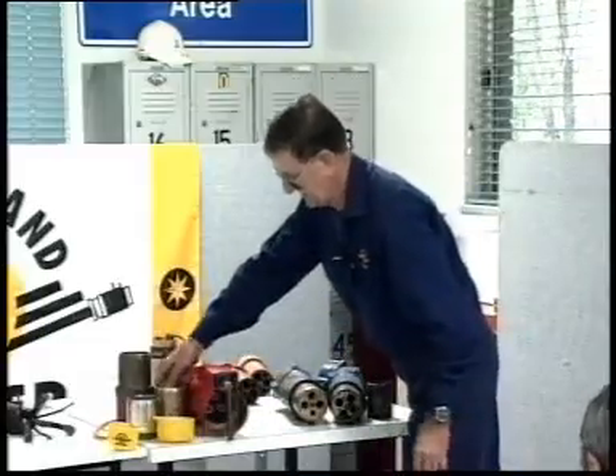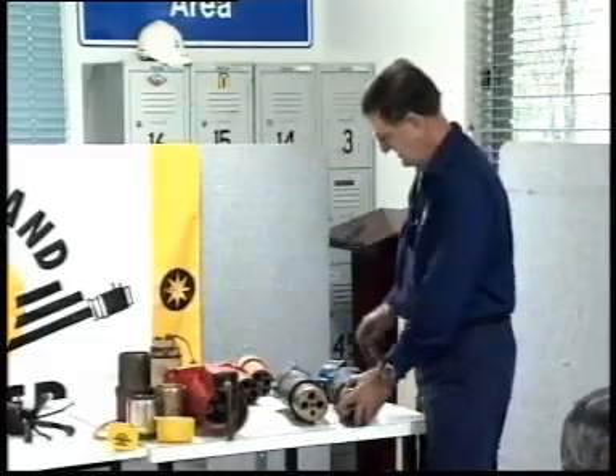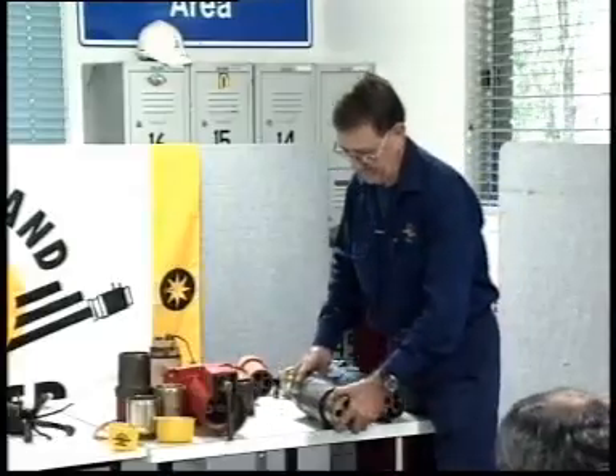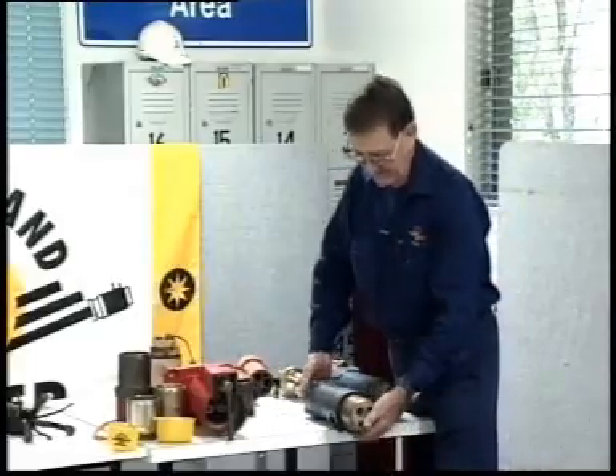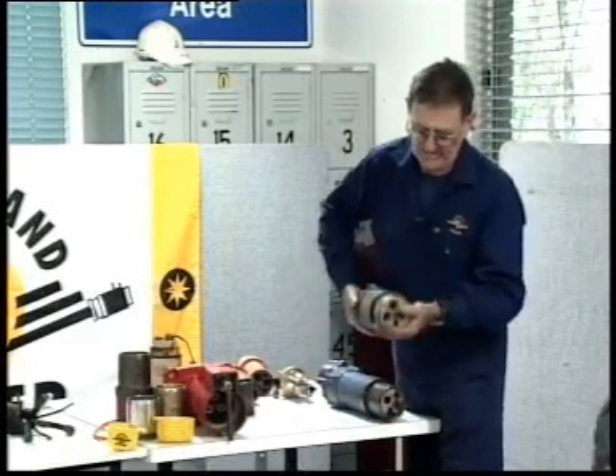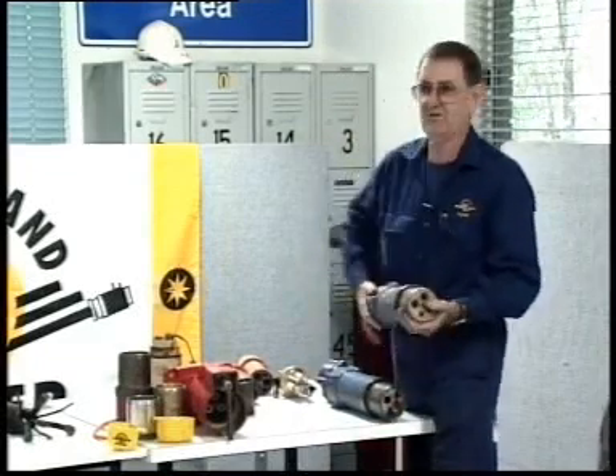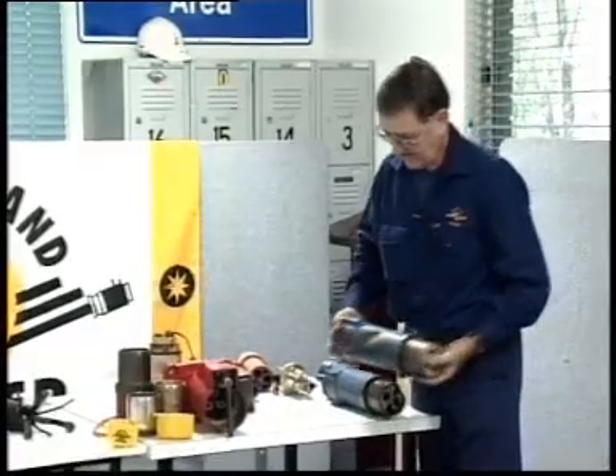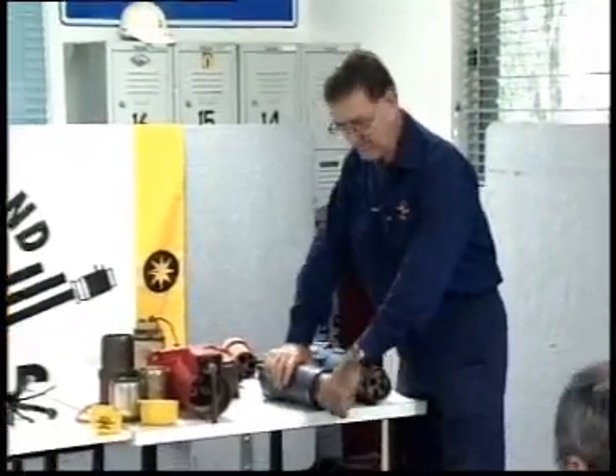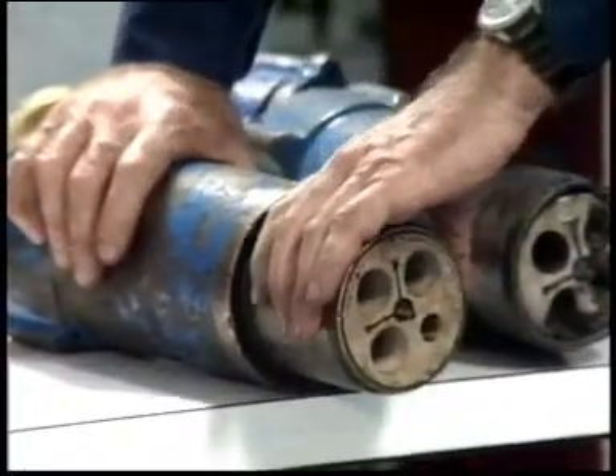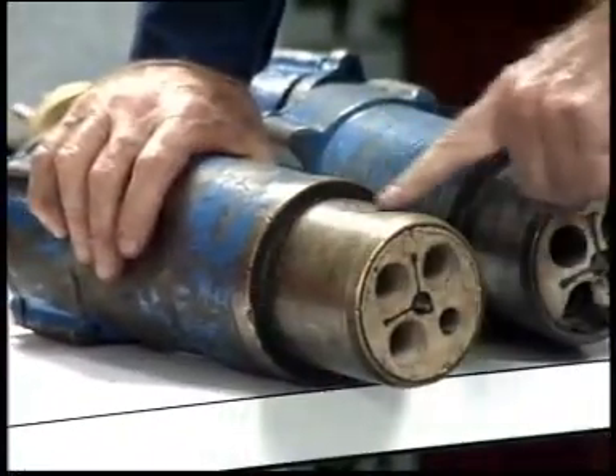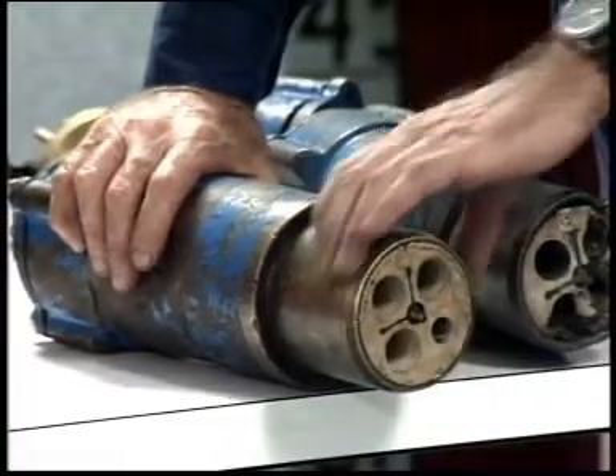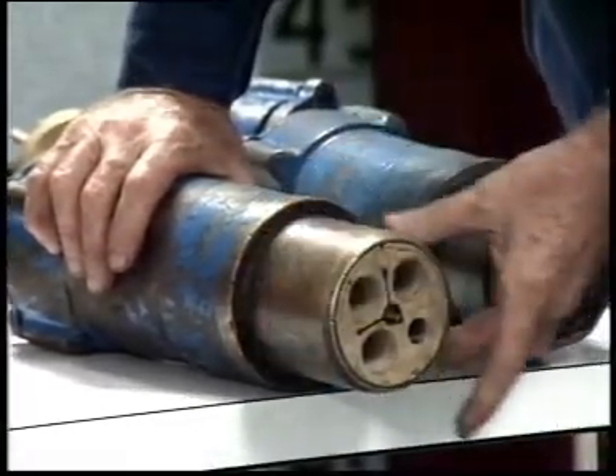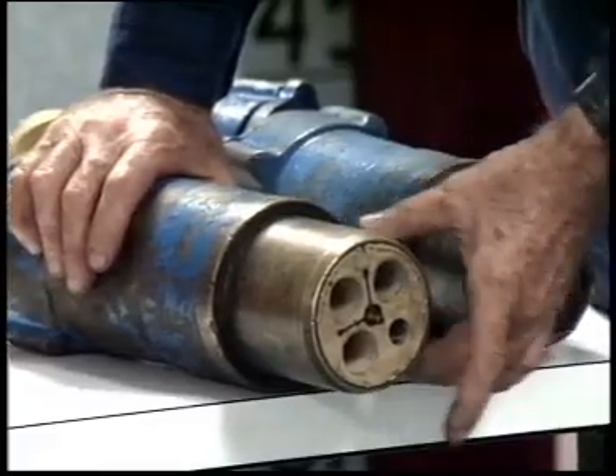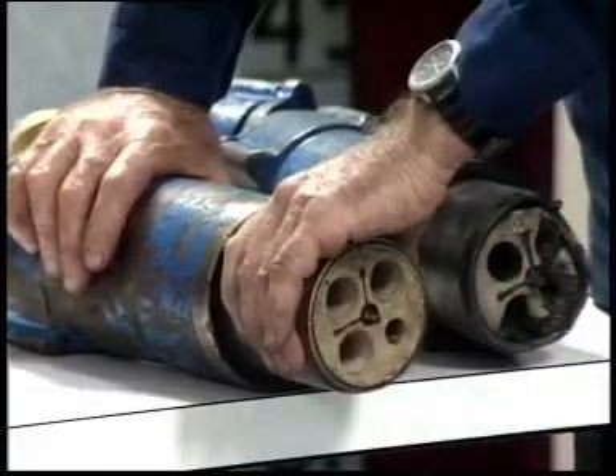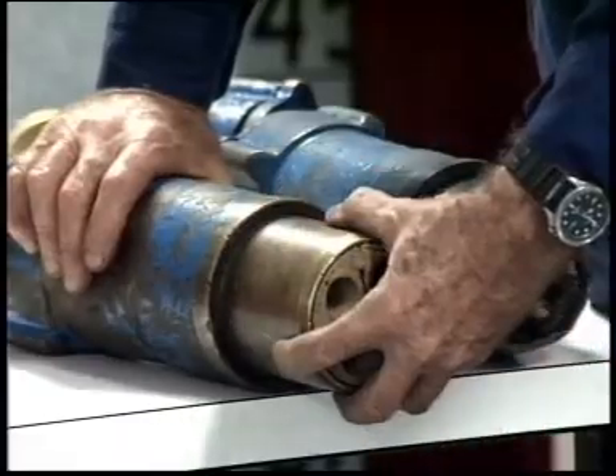Okay, we've looked at the receptacle or the back-to-back, as we explained before. We have a look at the plug itself. First thing we do when we pick the plug up, we have a look around it to make sure that the flame path looks reasonable. And that one looks reasonable. It doesn't have to be highly polished so you can see your face in it. A lot of people think that the more polish you put on things, the better they are, but we get guys getting stuck into these with emery, and they actually wear down that surface so that it no longer complies. When these come into town, we have what we call go and no-go gauges that we measure that with to make sure that it's within the Australian standard tolerances, is what it should be.